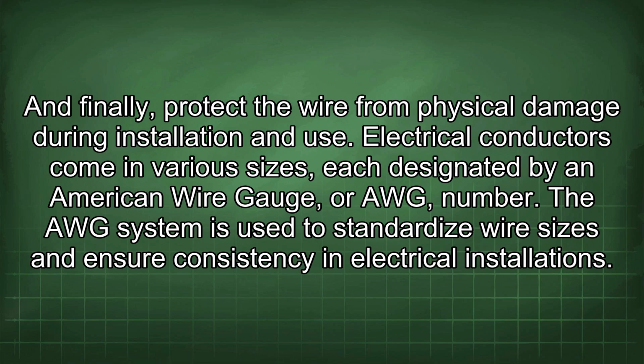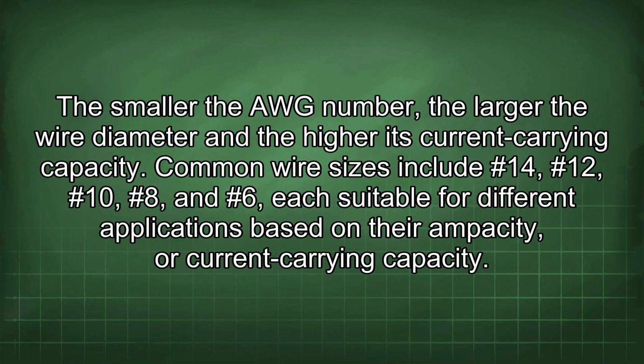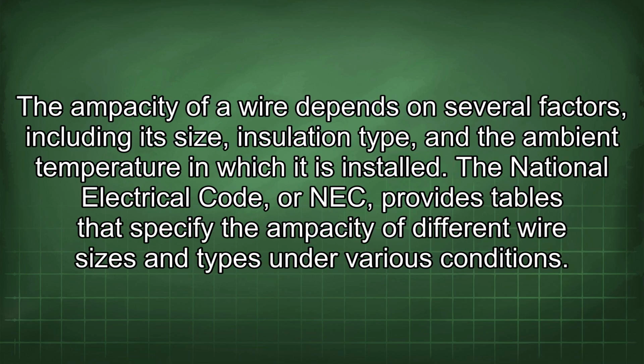Electrical conductors come in various sizes, each designated by an American wire gauge, or AWG, number. The AWG system is used to standardize wire sizes and ensure consistency in electrical installations. The smaller the AWG number, the larger the wire diameter and the higher its current carrying capacity. Common wire sizes include #14, #12, #10, #8, and #6, each suitable for different applications based on their ampacity, or current carrying capacity. The ampacity of a wire depends on several factors, including its size, insulation type, and the ambient temperature in which it is installed.